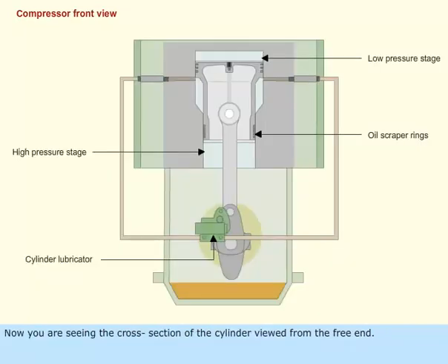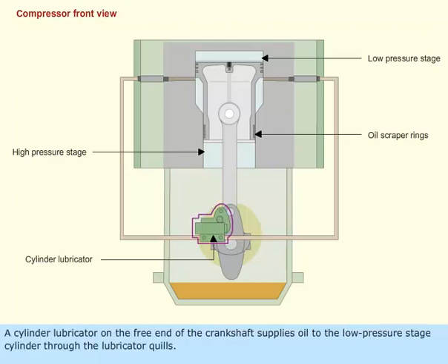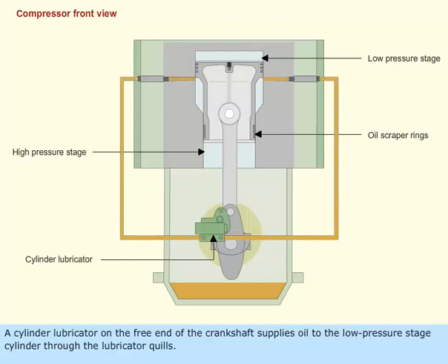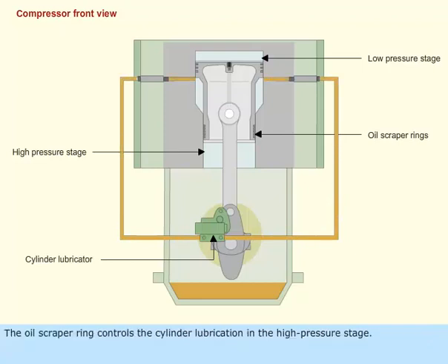Now you are seeing the cross section of the cylinder viewed from the free end. A cylinder lubricator on the free end of the crankshaft supplies oil to the low pressure stage cylinder through the lubricator quills. The oil scraper ring controls the cylinder lubrication in the high pressure stage.